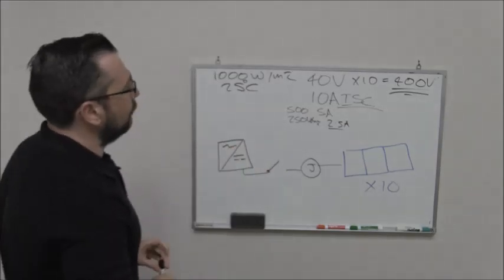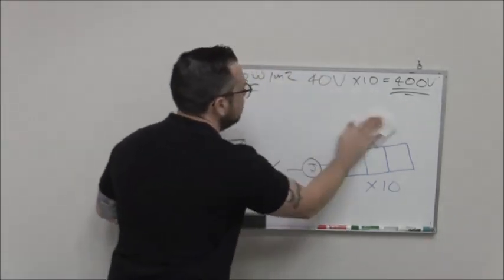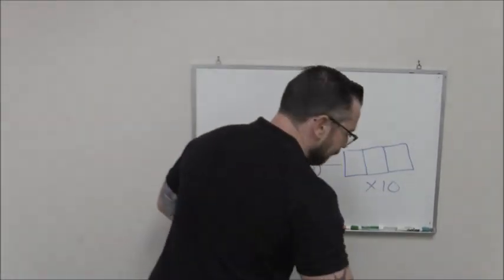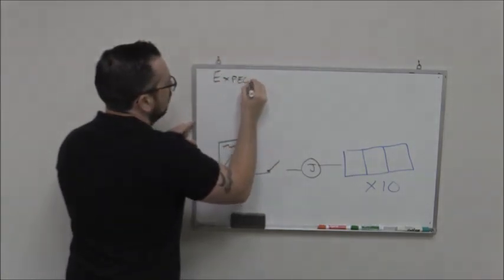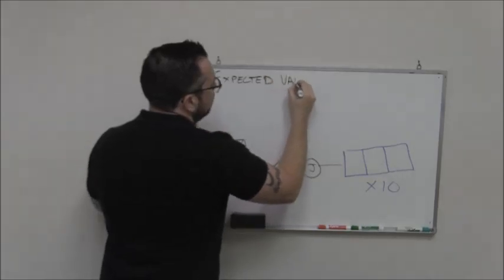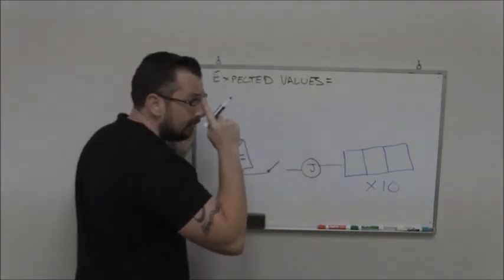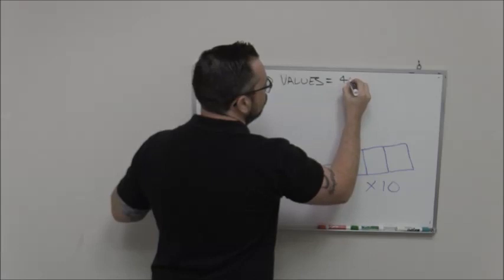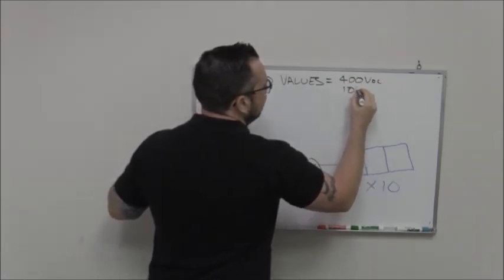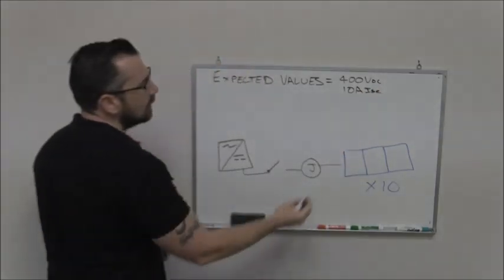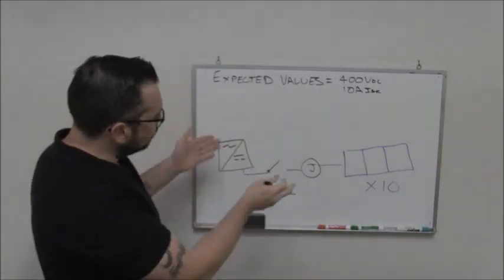So I have my expected values. I have 10 panels. And let's say for instance, it is 1000 watts per meter squared. So when I run my test, my expected values at 1000 watts per meter squared, 25 degrees Celsius, I should see 400 volts and I should see 10 amps. That's what I'm expecting to see when I run my test.